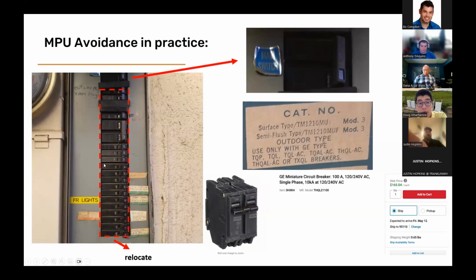So if you have to relocate these loads, you then use that specialized breaker. One thing to be on the lookout for when you're out doing a survey: make sure to capture the model and the type of breakers there, because that'll definitely help your design teams.